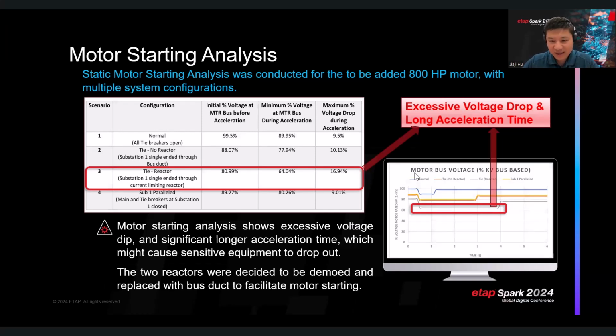So when we run the study, we can see from the curve here that our scenario number 3 with reactor and the system single-ended has the worst case that your voltage drop is over 17% and your motor terminal voltage when starting is barely about 60%. And you have a significant bigger motor acceleration time. So under this scenario, probably our sensitive equipment in the system can drop out. So it's considered a failed motor starting result. So the decision here is to remove the 2 reactors and replace it with a bus duct to facilitate a healthy motor starting.